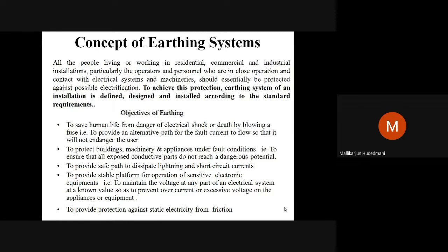Whenever that electrical gadget, maybe an iron box or a computer or a laptop, whatever it is, has a 3-pin contact, definitely the excess induced charge in the metal enclosure is driven to the earth pit, so that even though you touch the metal enclosure, you will not feel a shock. That is the provision called earthing. So earthing is providing an electrical contact from the metal enclosure of the electric gadget to the earth point, driving it to the earth point. The concept here is that current always prefers the low resistive path. If a human touches that, a human possesses 500 to so many kilo ohms of resistance, but the conducting wire possesses resistance in terms of ohms, so the current rushes through that first to the ground. Therefore, earthing is just providing an electrical contact from the metal enclosure to the earth pit, which definitely ensures safety.